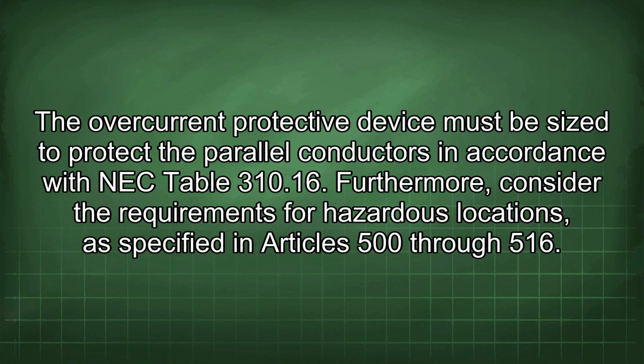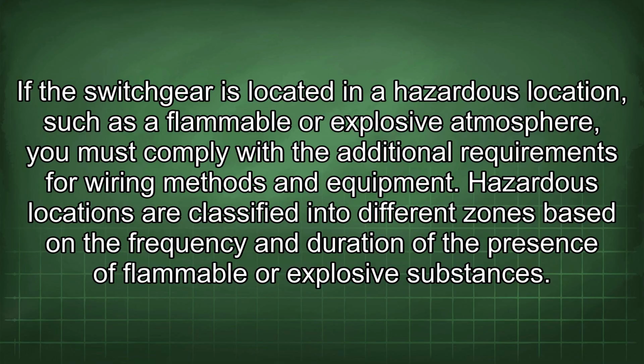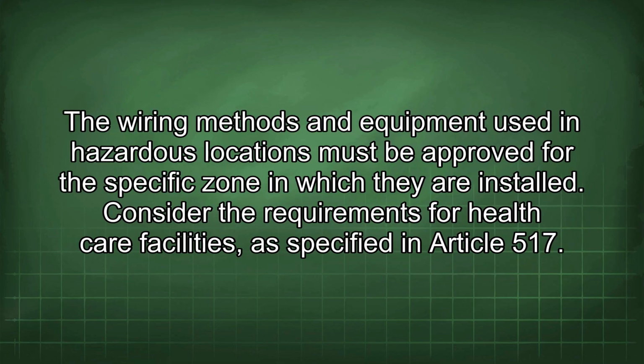Furthermore, consider the requirements for hazardous locations, as specified in Articles 500 through 516. If the switchgear is located in a hazardous location, such as a flammable or explosive atmosphere, you must comply with the additional requirements for wiring methods and equipment. Hazardous locations are classified into different zones based on the frequency and duration of the presence of flammable or explosive substances. The wiring methods and equipment used in hazardous locations must be approved for the specific zone in which they are installed.